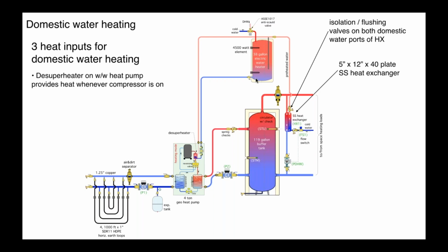When we ordered this heat pump, we ordered it with a de-superheater, which is a small heat exchanger that takes the hot gas directly from the compressor, and that hot gas passes through a portion of the primary side of that heat exchanger. The secondary side of that heat exchanger has domestic water passing through it. So we've got a pipe here. This is a 3/4 inch copper line coming from the lower connection on the water heater down. It goes through a stainless steel circulator that's part of the heat pump when you order it with the de-superheater. That circulator is already installed and wired. It operates whenever the compressor is running, with one exception: if the domestic water temperature leaving the heat pump reaches above 130, it will temporarily shut that circulator off. So that's basically just an upper temperature safety control.